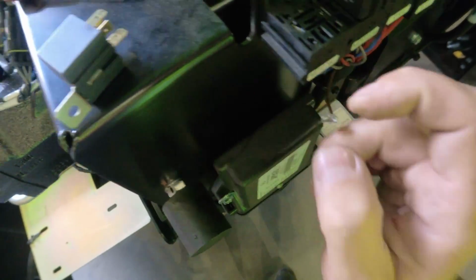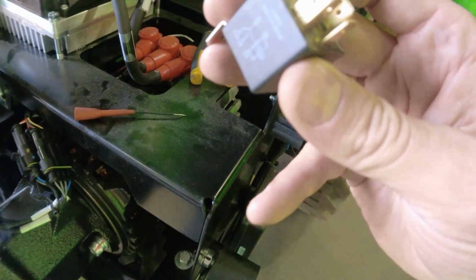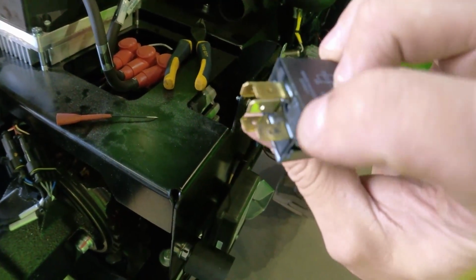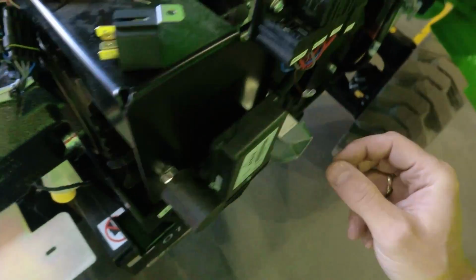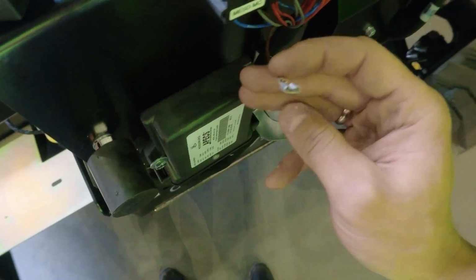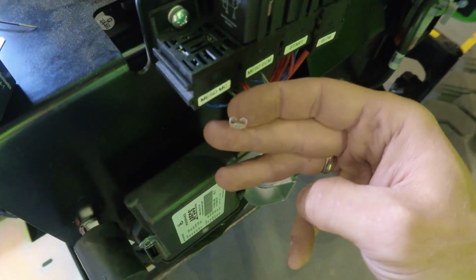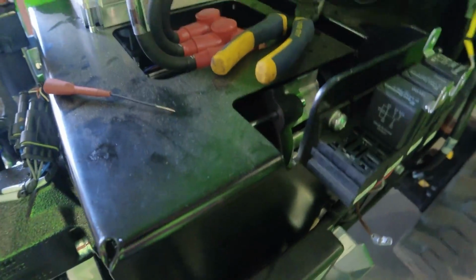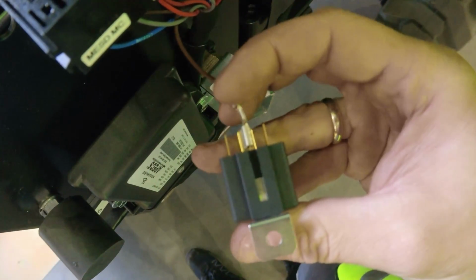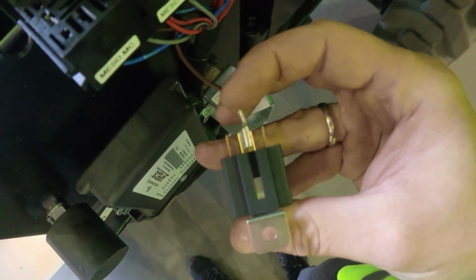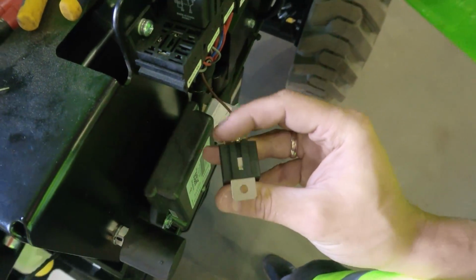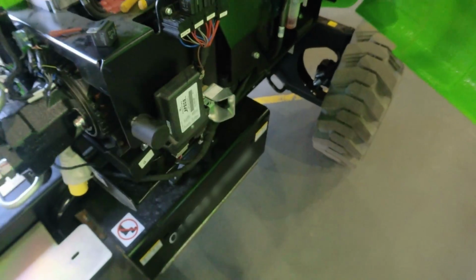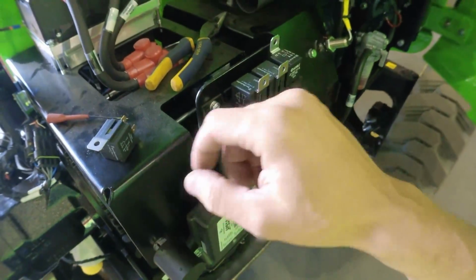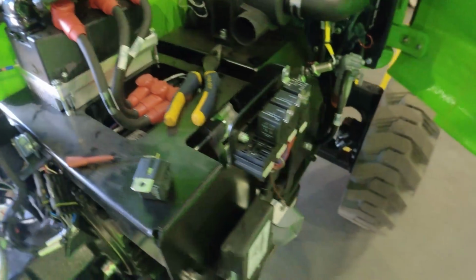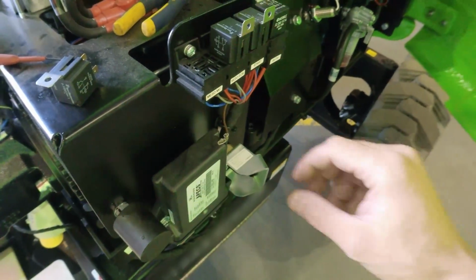That is for pin 30, and that's where we see all the arcing marks on pin 30, and you can see the pin is open too much, so it's too loose. Once it goes onto the relay, there is a lot of play on it, so it's not making good contact, and that's what's causing the trouble. As the machine moves around, the relay vibrates and it can drop out on the motor controller and give the random errors. So that's kind of an easy fix.